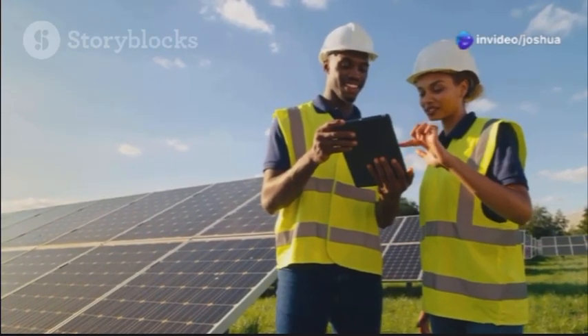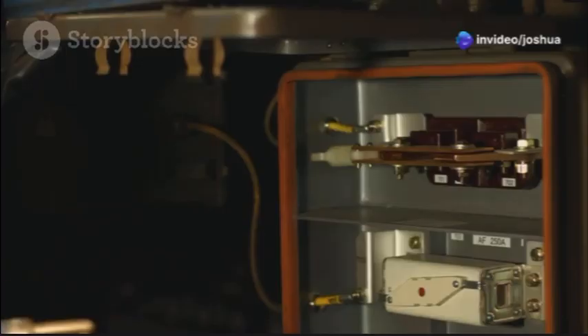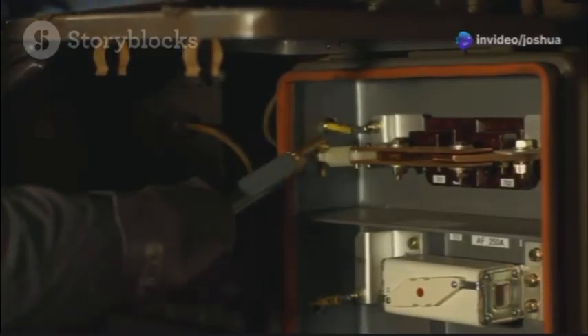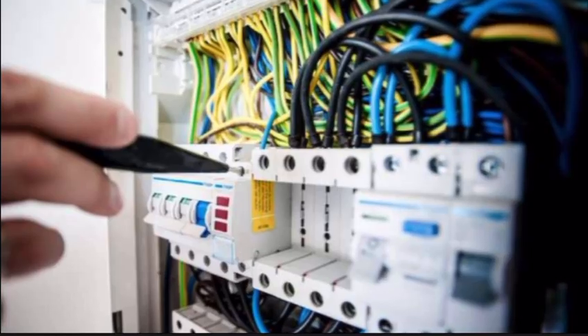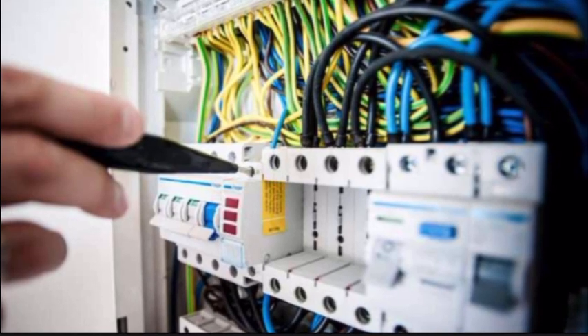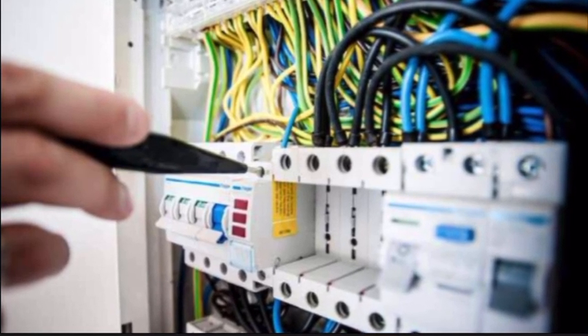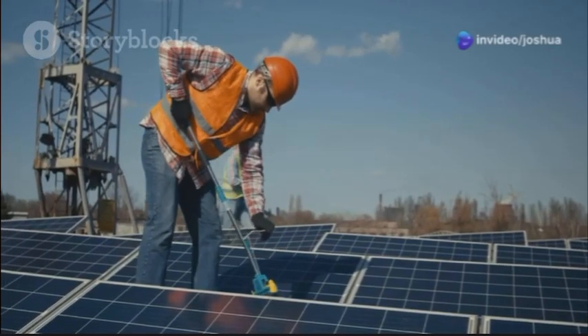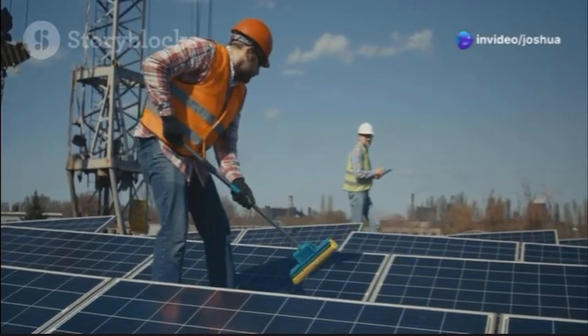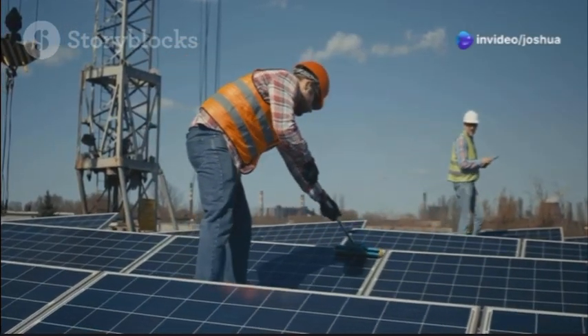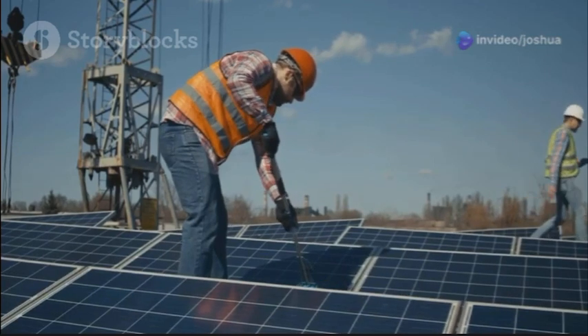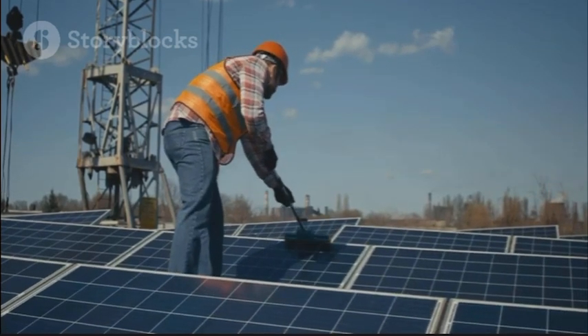Here are some common issues and quick fixes. If your inverter isn't turning on, check the circuit breaker, all connections, and fuses to make sure everything is secure and functioning. If you're seeing low energy production, clean the solar panels, check for any new sources of shade like growing trees, or contact your installer for a professional assessment.